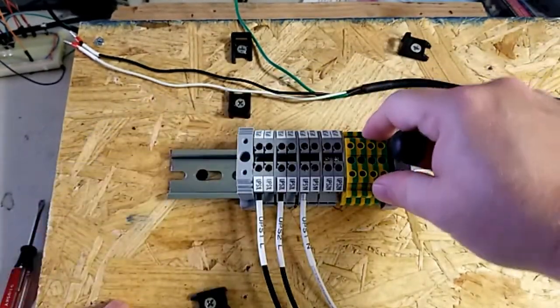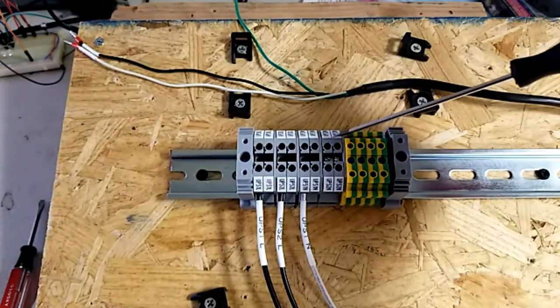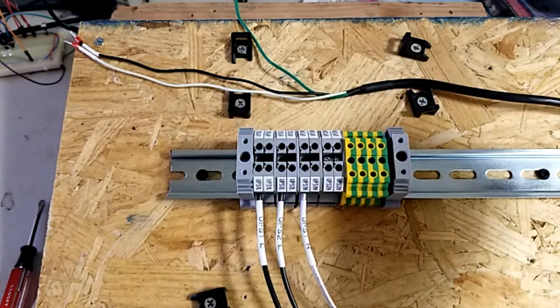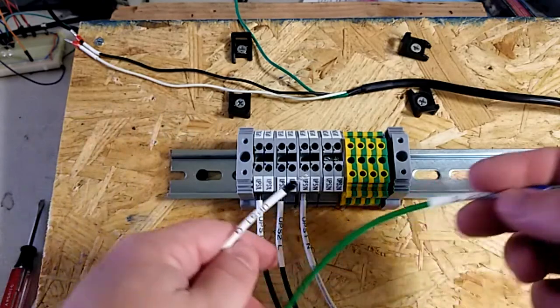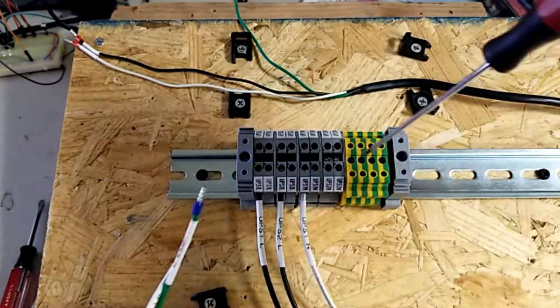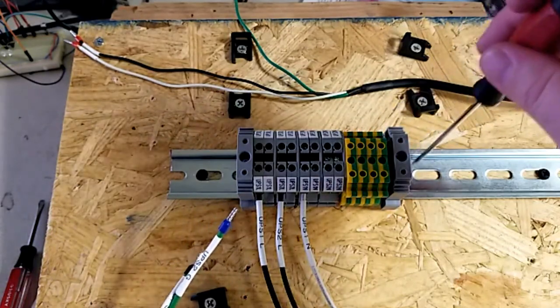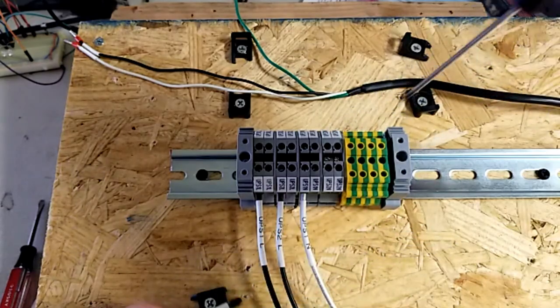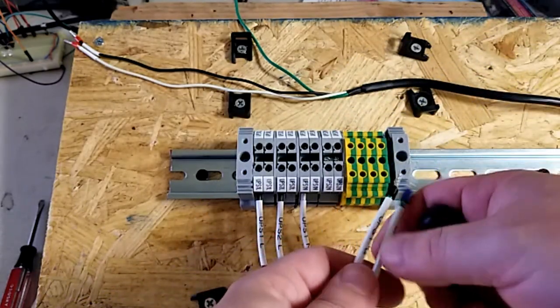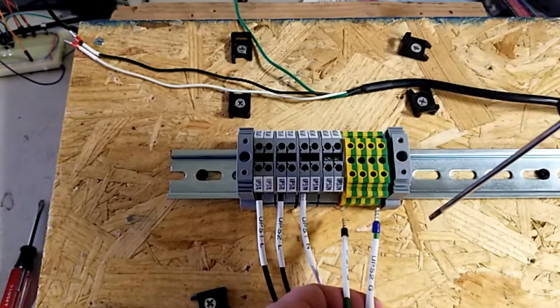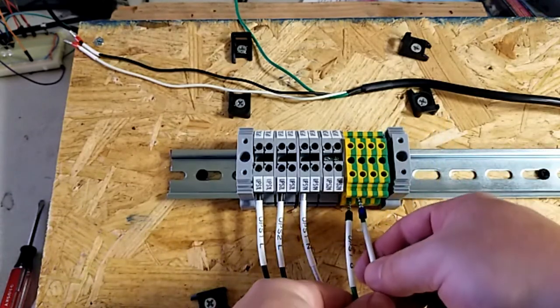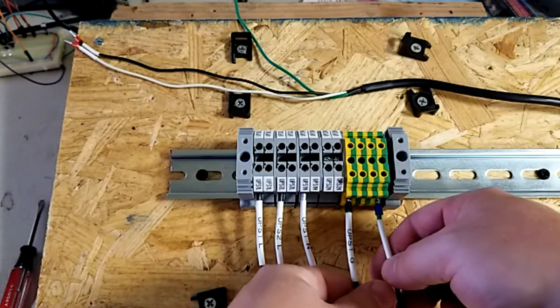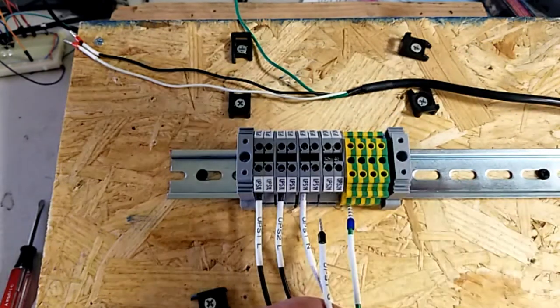Okay, so now our new grounding blocks are in place and our new replacement neutral terminals are in place. So from here now, I can rewire all of my existing ground wires. So these ground wires, because they clamp down tight to this bar, they are electrically connected to this bar. They're electrically connected to the ground plane. So it does not matter now which hole you wire any of your ground wires. So all of your green ground wires just need to go into any of these ground terminals because they're all electrically the same.